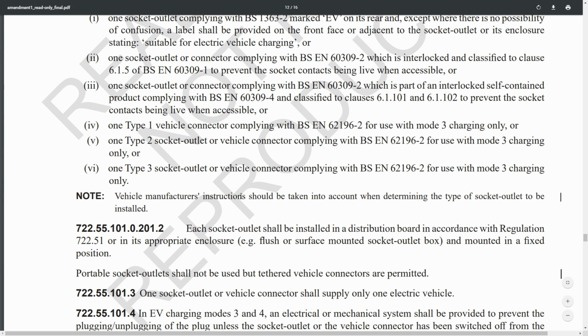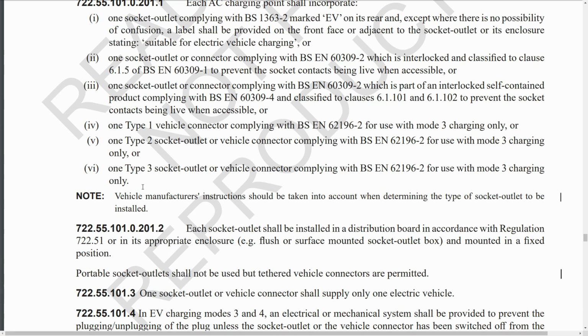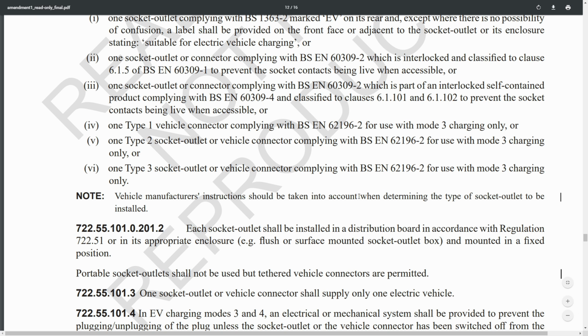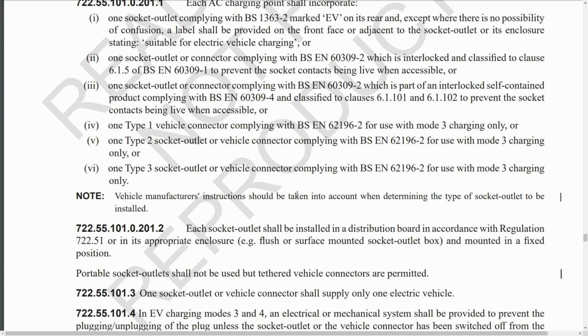And we've got a note here about vehicle manufacturer instructions should be taken into account when determining the type of socket outlet to be installed, because although there's supposed to be one standard for all vehicles, well guess what, some manufacturers use different ones. So again, pretty straightforward stuff there. That was actually in there before, but again it's one of these that's been a minor adjustment, so nothing has really changed. It now says should be taken into account, and previously it said should be followed. So followed basically means you will comply, and taken into account means, well, you should certainly consider it, but if the manufacturer instructions turn out to be a load of nonsense, then not necessarily to actually continue following them to every detail. But in reality, if a vehicle has a particular type of connector, then of course you're going to be installing the charge point appropriate to that vehicle, certainly if it's one that's going to be used, say, in a domestic environment where you know what kind of vehicle it's going to be.